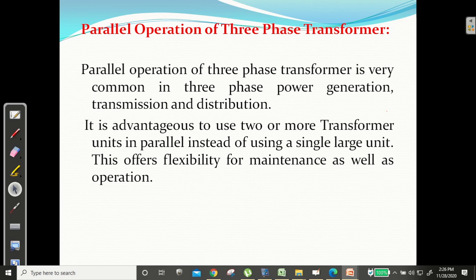Second, suppose a large transformer is installed and the load reduces to say 10%. Iron loss, which is a constant loss, will still continue regardless of load, which is simply a wastage of money, so losses will be more compared to actual requirement.